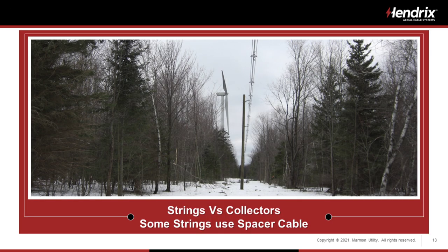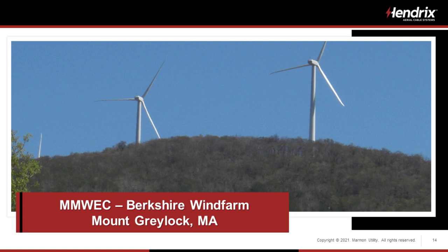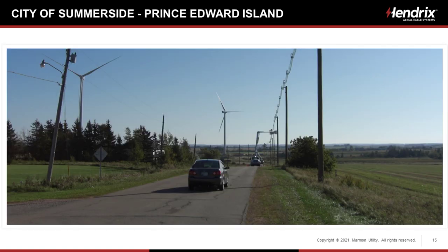And I said strings versus collectors. Some of the strings in that wind farm were spacer cable, and that was because we were trying to minimize the foliage and the tree removal between those individual turbines and the 34.5 kV collector circuits. There's another job we did. This is what we call old growth in New England. This is Berkshire Wind Farm up on Mount Greylock. So some of those strings were underground cable. All the collectors were spacer cable.